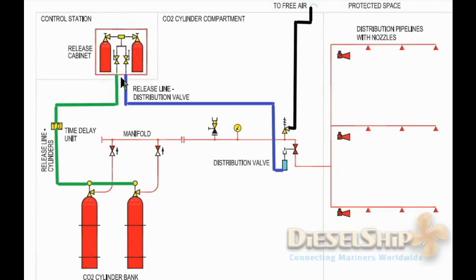The valve control station can be located at different places, but definitely outside the space to be protected. Here the protected space is the engine room, so it must be outside the engine room; otherwise you can't operate it in the event of fire. There are three possibilities for location: the fire control station, the CO2 room itself, and just outside the entrance of the engine room.